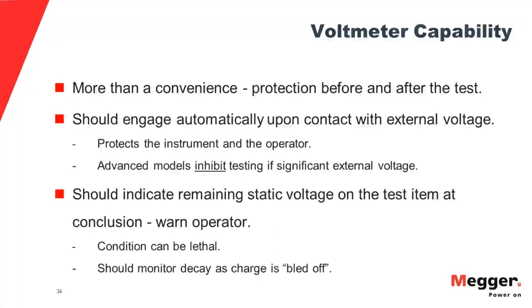That will charge up, and that will be stored at the end of the test. The operator goes up and tries to disconnect the leads and accidentally gets across the voltage. That can be lethal. A good quality modern tester will automatically begin a discharge circuit and tell the operator that that's happening. So all you have to do is look at the display, and it will tell you what is going on. Okay.